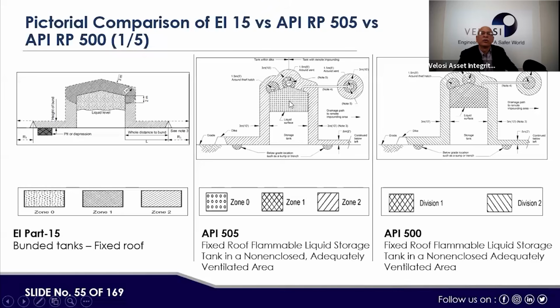Similarly, the same configuration is there in API 505. If you see here, zone 0, then zone 1, and this is the difference here. They are taking up to 3 meters, and up to the dikes is zone 2. In IP-15 or EI-15, they did not show the breathing valves, or there could be breathing valves, normally nozzles on the top.